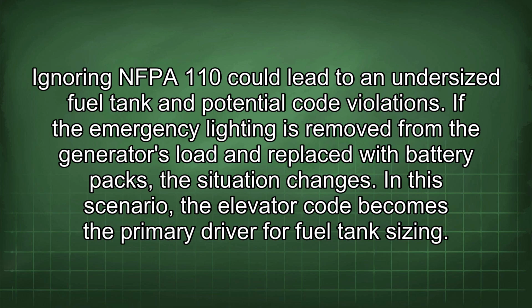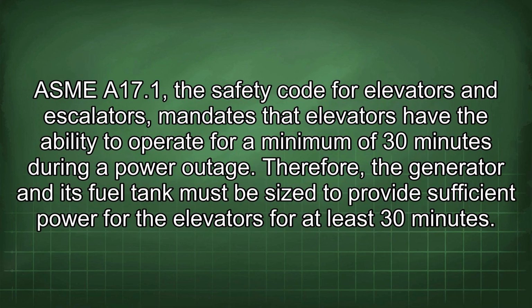If the emergency lighting is removed from the generator's load and replaced with battery packs, the situation changes. In this scenario, the elevator code becomes the primary driver for fuel tank sizing. ASME A17.1, the safety code for elevators and escalators, mandates that elevators have the ability to operate for a minimum of 30 minutes during a power outage.